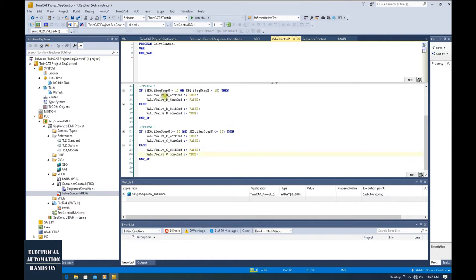And take care here. If you use the individual step numbers, basically we will OR all the conditions. Another way that actually makes it easier is this: use the greater or equal, or less than or equal, and use the AND. Make sure that it is only within this step number range to turn this C, to turn the valve on or off.